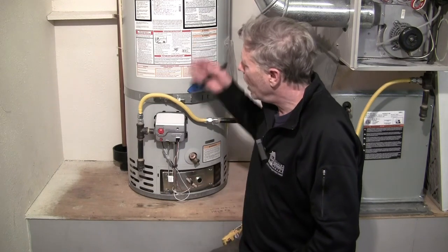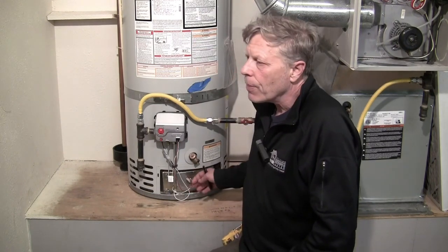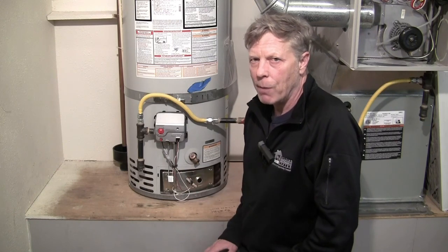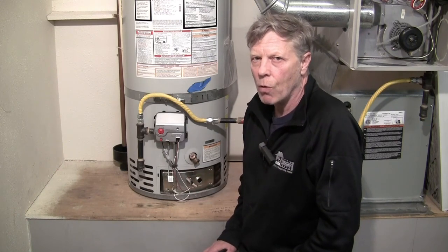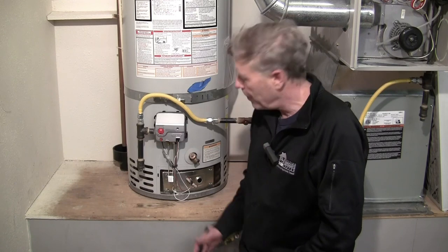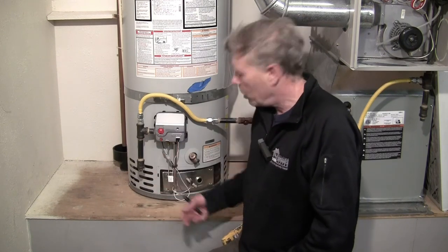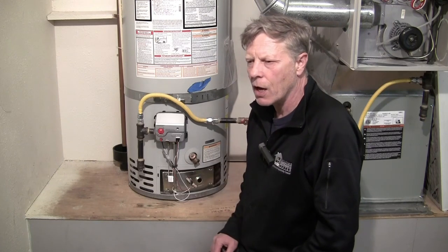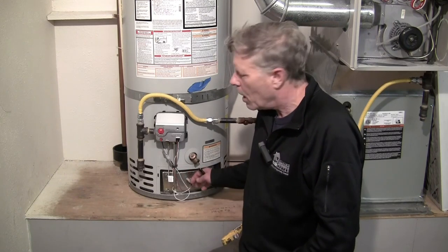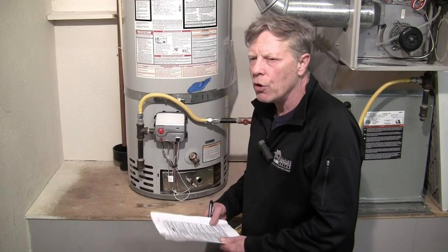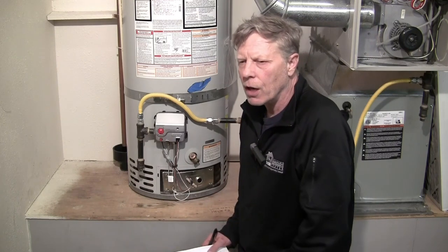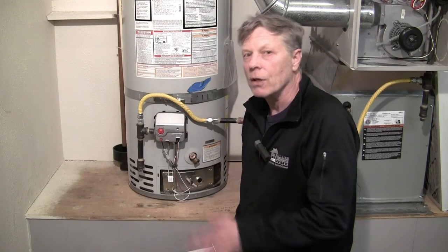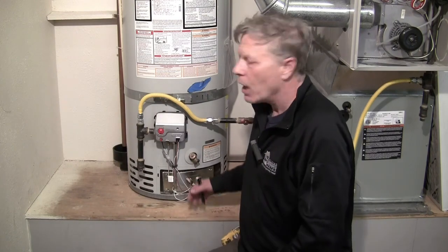But they made this type of water heater to protect from that. This is called the Flammable Vapor Ignition Resistant Water Heater, FVIR. And it would be allowed to be on the floor because it's all blocked off in here and it will resist igniting the vapors. Generally, you will see water heaters 18 inches off the floor in garages, but if it isn't, that's a fail.